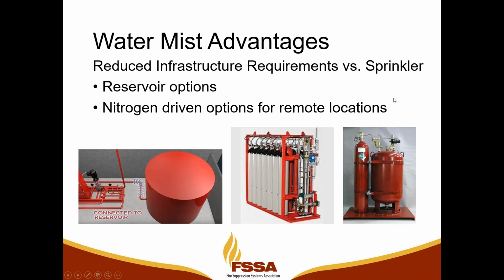Another advantage of water mist when we talk about infrastructure, and Jonathan alluded to this, is that when we've got a remote location where we may have an inadequate water supply, we may even have an electric supply that's not suitable without upgrade for a sprinkler pump or a water mist pump, we have the ability to use a containerized water mist system that's got a smaller than normal reservoir. So you see two examples of that in the middle and on the right.